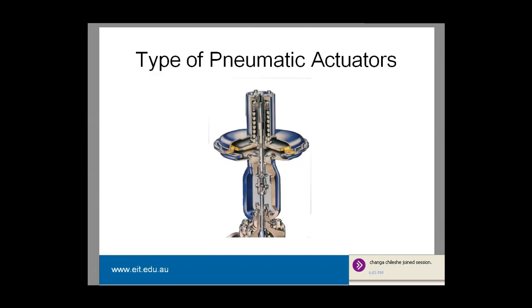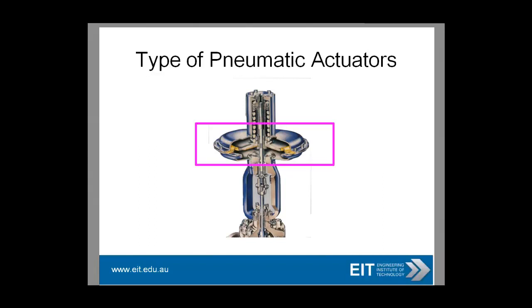We're going to get different types of pneumatic actuators. In the early days, learning in the field of instrumentation, the diaphragm type was the most popular type of actuator in our industry. They were great for fine control, but had a reduced stroke length — that arm wouldn't move all that much. They had relatively low thrust, were maintenance-prone, bulky, could not operate at higher pressures, and field reversal — changing from air-to-open to air-to-close — was not always possible. They were generally operated with a signal of 20 to 100 kilopascals. Precise control required a valve positioner.